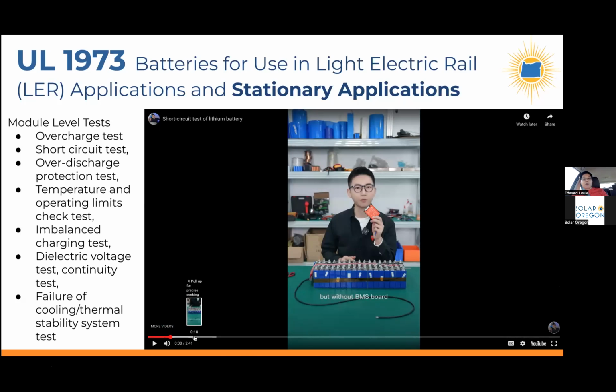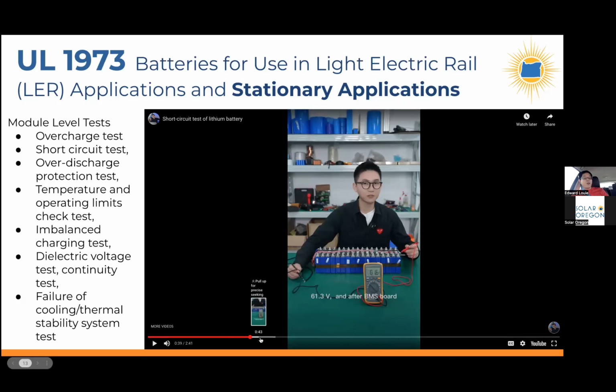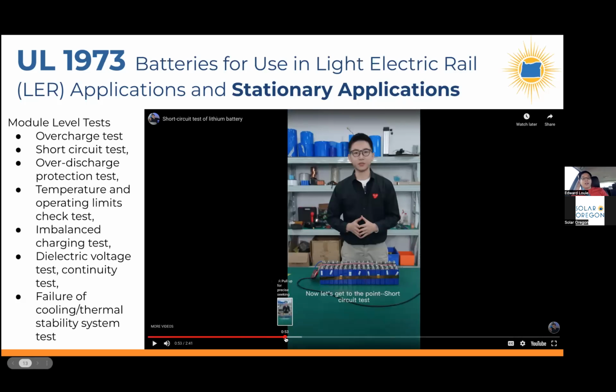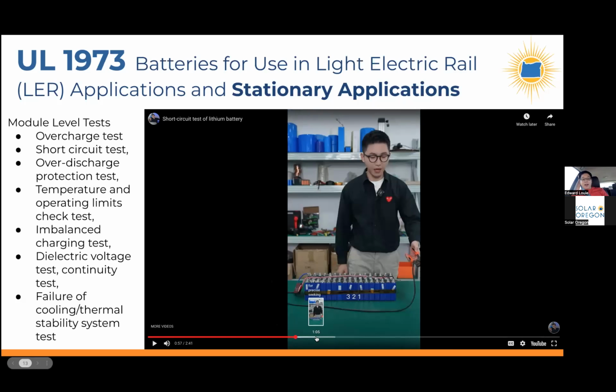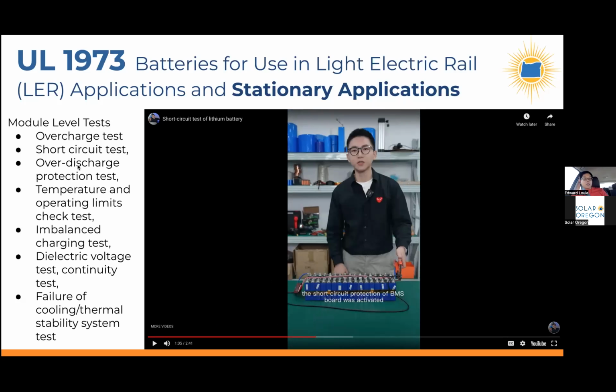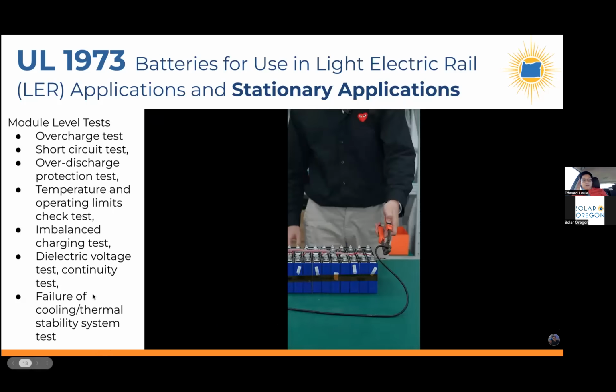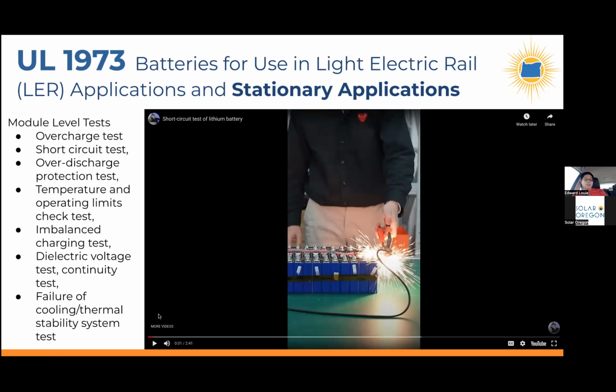He does explain in this video that if the BMS was not present and you just dead short the cells, he would not be willing to stand next to it to do the test. And I wouldn't either, because the failure could be much more dramatic. And that's just the short circuit test. There are other tests that need to be done. The UL 1973 test outlines these tests, and they're all done, and they come out as a report on the safety of what they find from these different tests in the 1973 report. So yeah, you get some sparks from the shorts, but it's not a whole thermal runaway or anything like that.